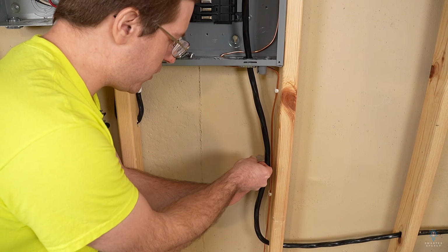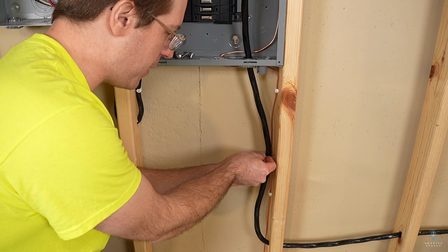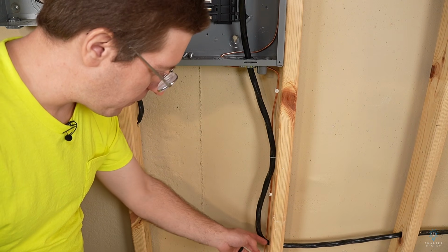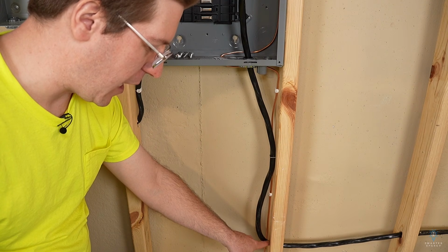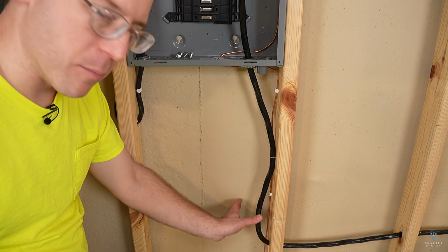So within 12 inches of the panel, we install one of our staples. And again, we do have to have this curvature here, otherwise we would kink the wire and break the insulation. We don't want to deal with that.